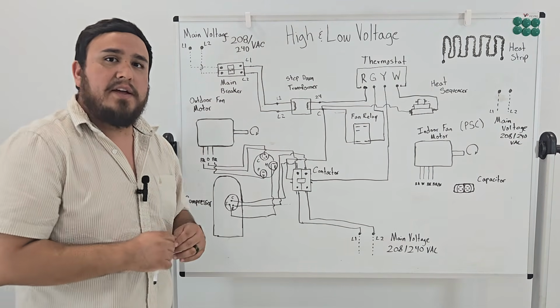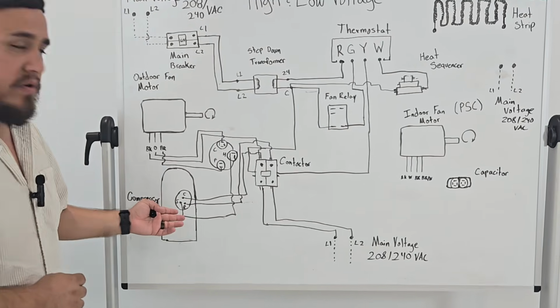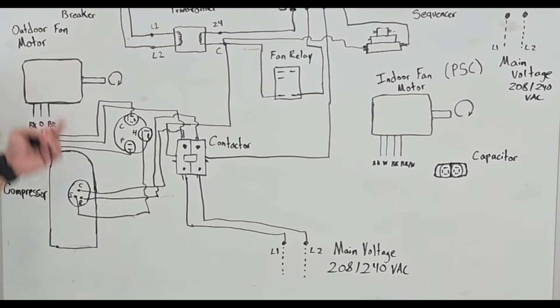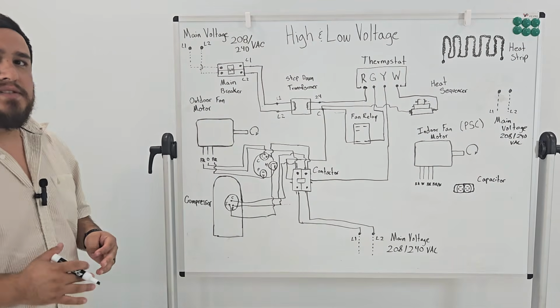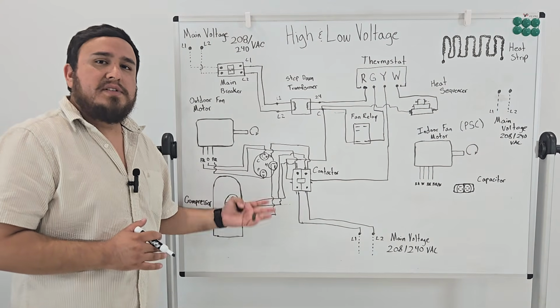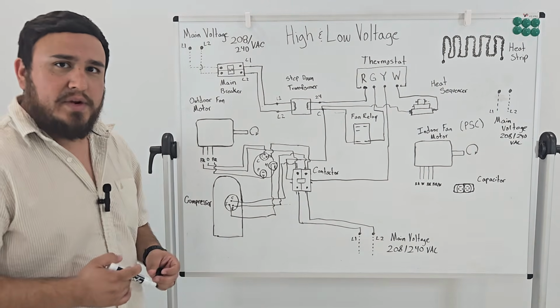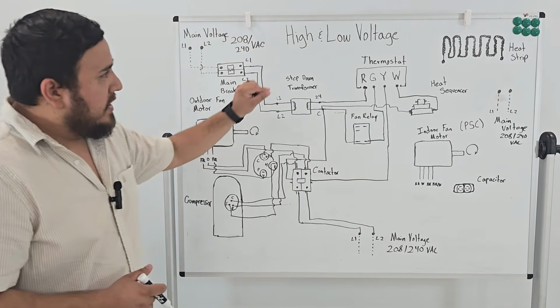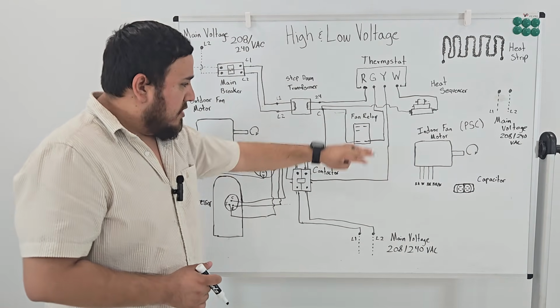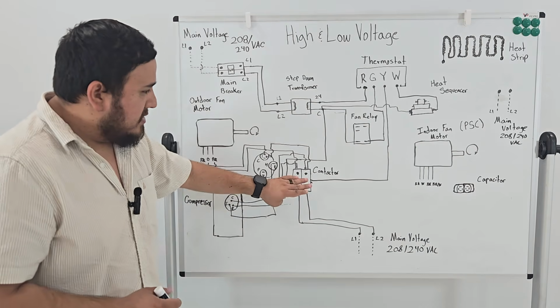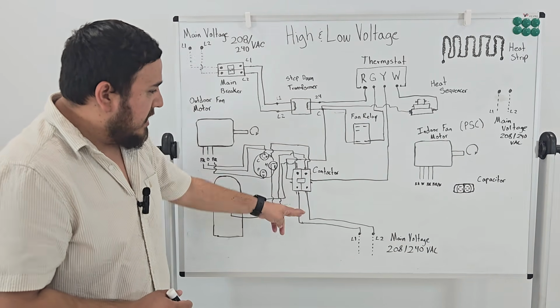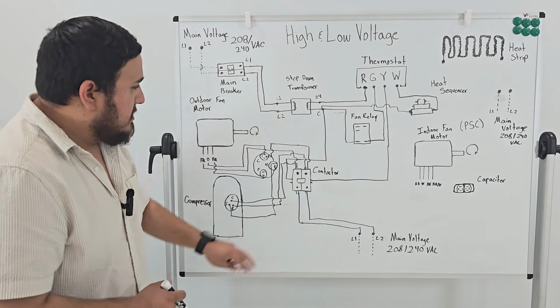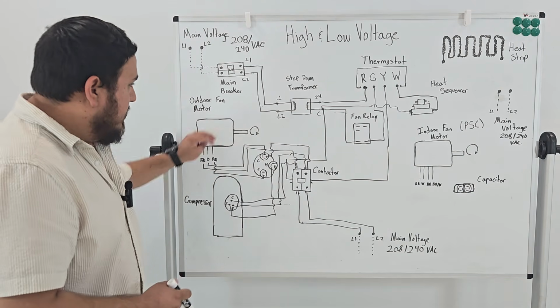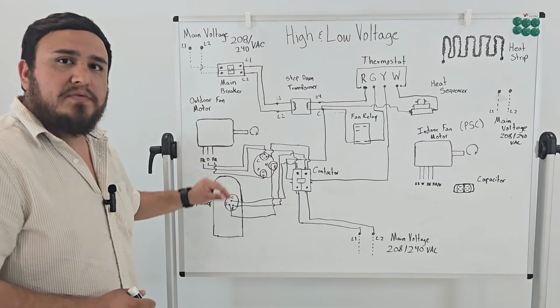I still need my other side, or my line 2, to be able to power my compressor and my outdoor fan motor. So let's go ahead and connect that. Okay, now I have successfully connected the outdoor system for my air conditioning unit. Now if I turn it on and press cooling, if my 24 volts are being sent to the contactor, that contactor is going to engage, the high voltage is going to travel straight through, and it's going to send all the voltage to where it needs to go. So all my components, in this case all my loads, function the way they need.